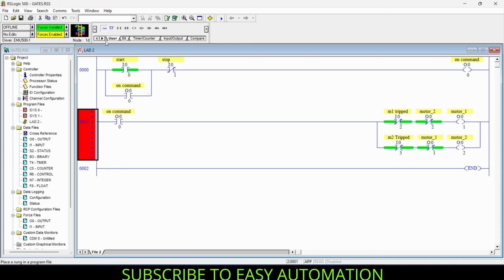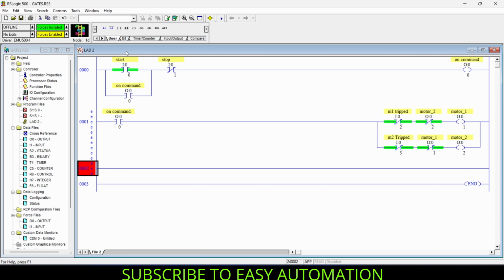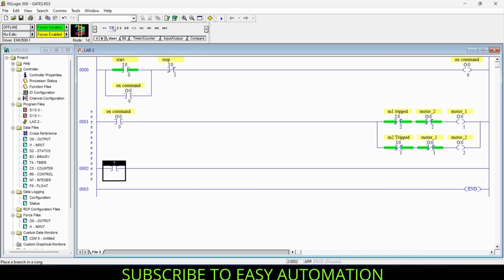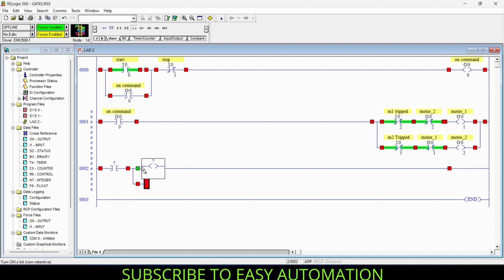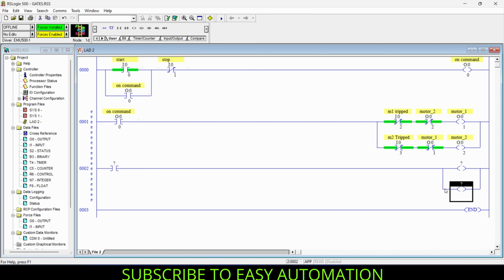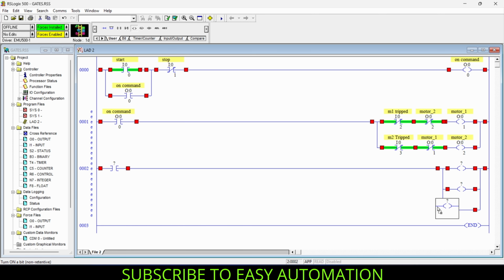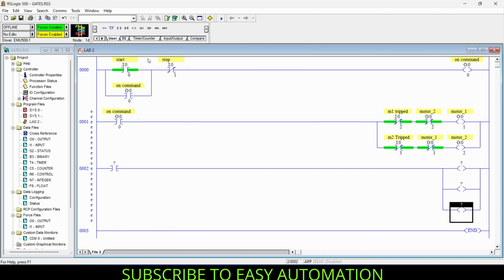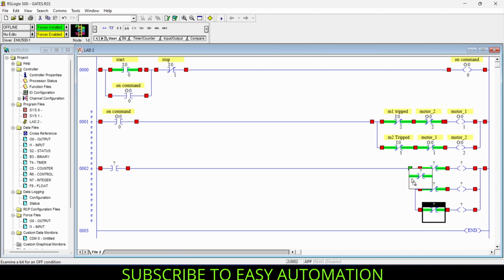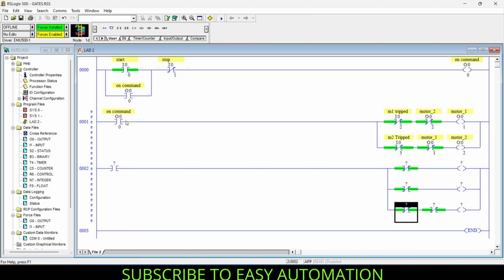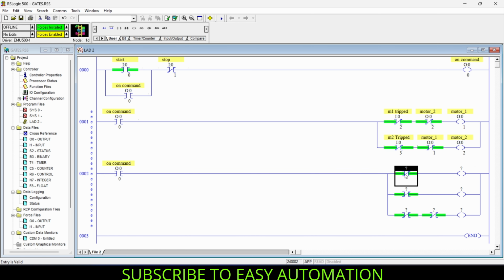And now for trip indication, I will add one another rung here and add one NO contact here and one branch instruction and one output coil and one another output coil, and I will just extend this branch down for the overall failure. I will add one another output coil for overall failure and add one NC contact in every branch, and for the last branch I will add one another NC contact. So for this NO contact I will just copy this on command here, and for these NC contacts I will just drag the first motor's address and the second motor's address.